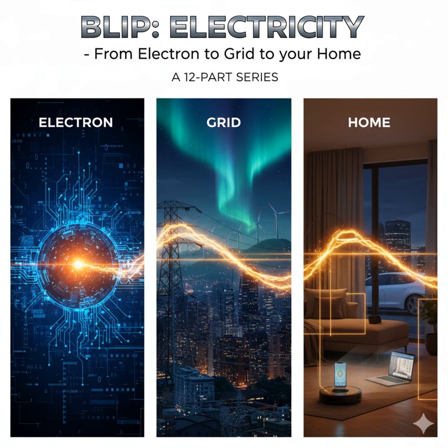How does it do that? What's the technology inside? It uses power electronics, specifically a voltage source converter, or VSC. Think of it as a very sophisticated inverter, similar to what you find in solar installations or variable speed drives, but operating at high power levels. And this VSC creates a voltage. Yes, the VSC generates an AC voltage waveform that's synchronized with the grid voltage in frequency and phase. The magic happens by controlling the magnitude of the StatCom's internal voltage relative to the grid voltage.